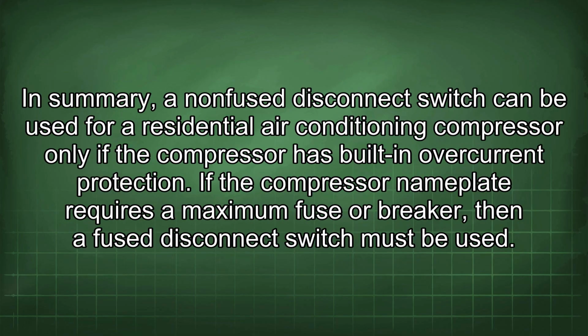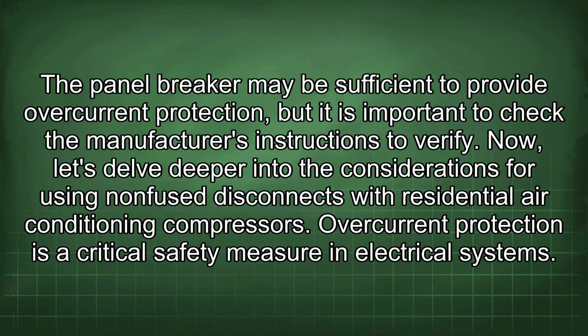In summary, a non-fused disconnect switch can be used for a residential air conditioning compressor only if the compressor has built-in overcurrent protection. If the compressor nameplate requires a maximum fuse or breaker, then a fuse disconnect switch must be used. The panel breaker may be sufficient to provide overcurrent protection, but it is important to check the manufacturer's instructions to verify. Now let's delve deeper into the considerations for using non-fused disconnects with residential air conditioning compressors.